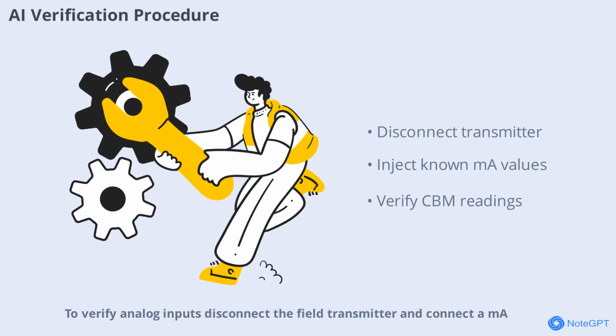Verify analog inputs. Disconnect the field transmitter and connect a mA loop calibrator directly to the AI module terminals. Inject known values 4, 8, 12, 16, and 20 mA, corresponding to 0%, 25%, 50%, 75%, and 100% of the range. The control room engineer checks that both the raw value and the scaled engineering value in CBM match the injected current perfectly. This procedure ensures that analog inputs are calibrated and functioning as intended.